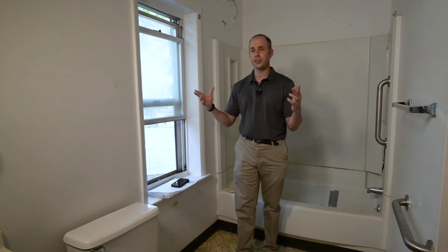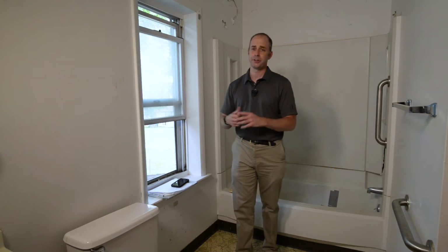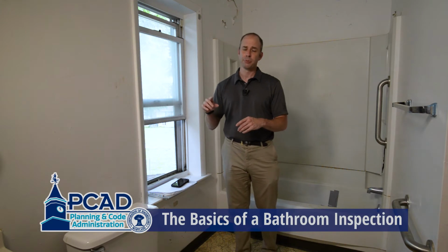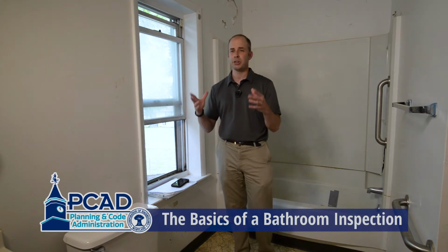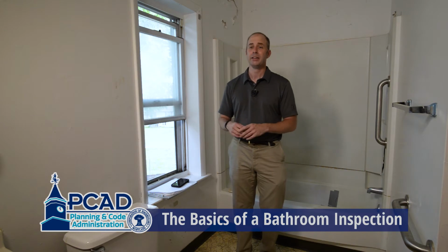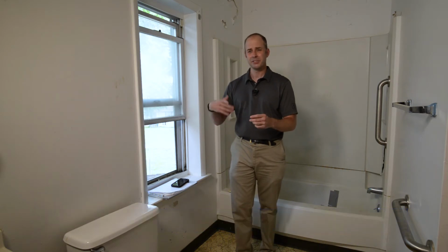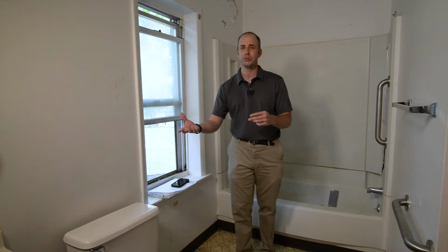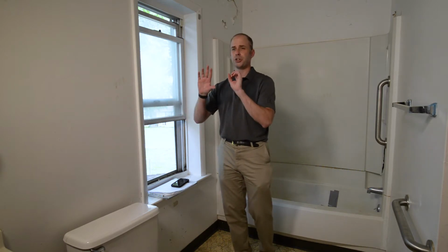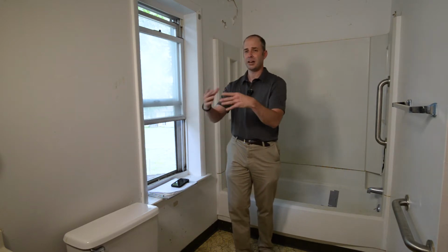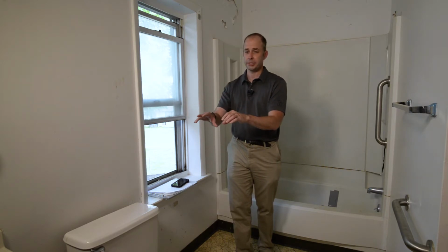One of the things is also electric. We're going to be looking at the outlets that are in a bathroom. Every bathroom is required to have one outlet, and it's got to be ground fault protected, or GFCI. When we're looking at the outlet, we want to make sure that there are no burn marks on it, that there isn't any melting of the outlet, there's nothing blocking the outlet from being properly used. Everything of those aspects, making sure that you can actually use the outlet, and then it trips and resets and functions with our testers, to make sure that if a circuit interrupt needed to occur because of an issue, it functions properly.